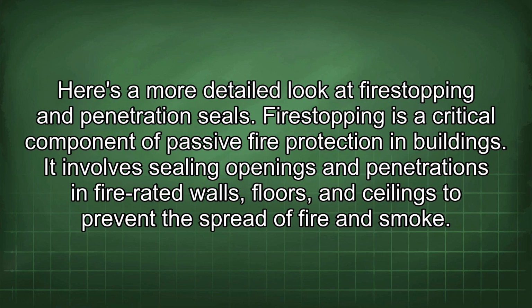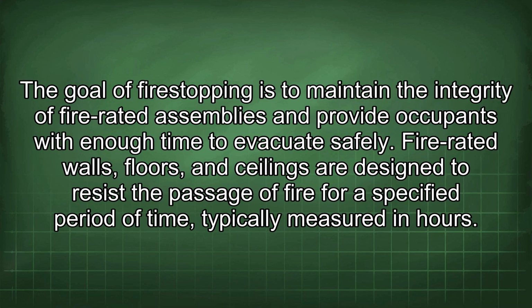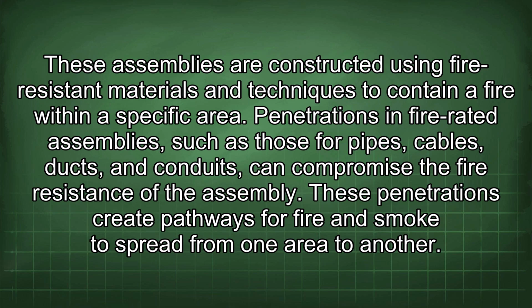Here's a more detailed look at firestopping and penetration seals. Firestopping is a critical component of passive fire protection in buildings. It involves sealing openings and penetrations in fire-rated walls, floors, and ceilings to prevent the spread of fire and smoke. The goal of firestopping is to maintain the integrity of fire-rated assemblies and provide occupants with enough time to evacuate safely. Fire-rated walls, floors, and ceilings are designed to resist the passage of fire for a specified period of time, typically measured in hours. These assemblies are constructed using fire-resistant materials and techniques to contain a fire within a specific area.